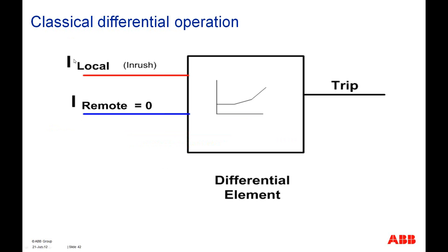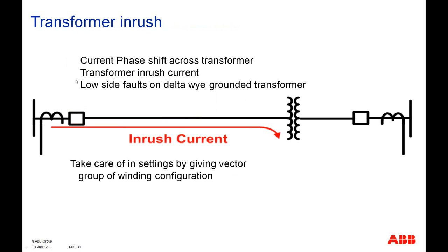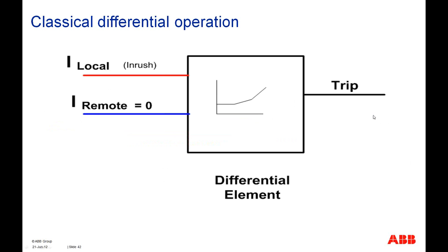So this diagram actually shows you the situation for the inrush current. As we can see over here, if this is the local station, then inrush current is felt over here, but not on the remote end. Therefore, we will have an unwanted trip, which we really need to avoid.